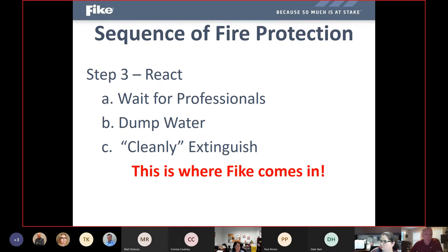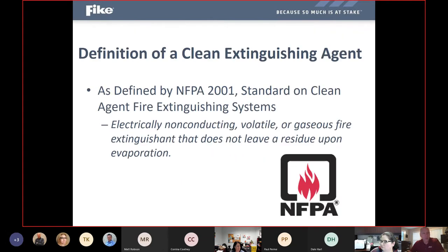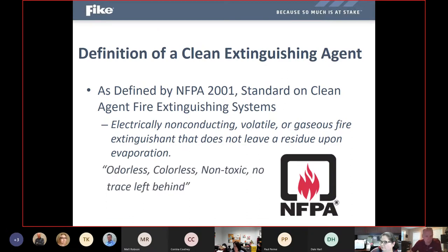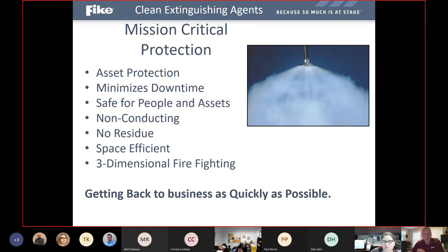And again, this is where Fike comes in. Through our broad product offering of clean extinguishing agents, which are defined in NFPA 2001, Standard on Clean Agent Fire Extinguishing Systems, it basically can best be described as anything you're using to put out a fire that is odorless, colorless, non-toxic or safe for exposure, and does not leave any trace behind. So no residue, no film, no dirt or dust to clean up or wipe up afterwards. It falls into the definition of a clean extinguishing agent.